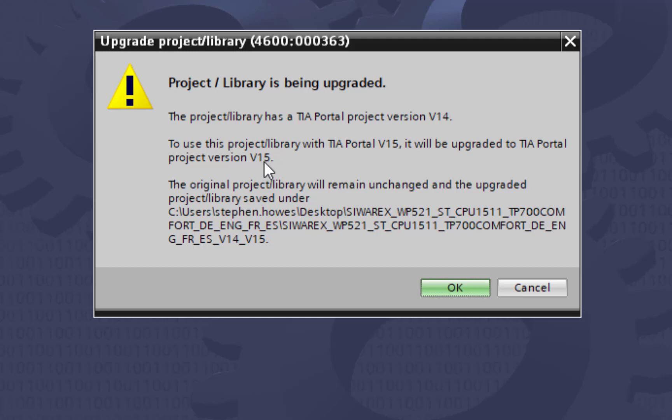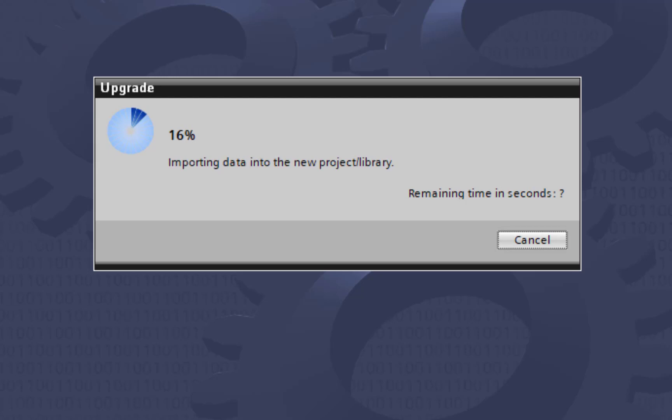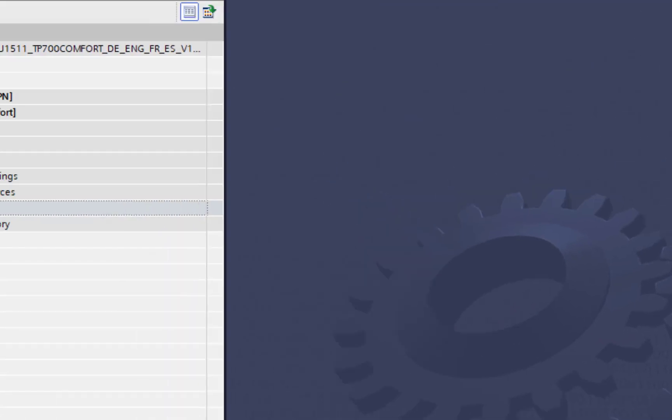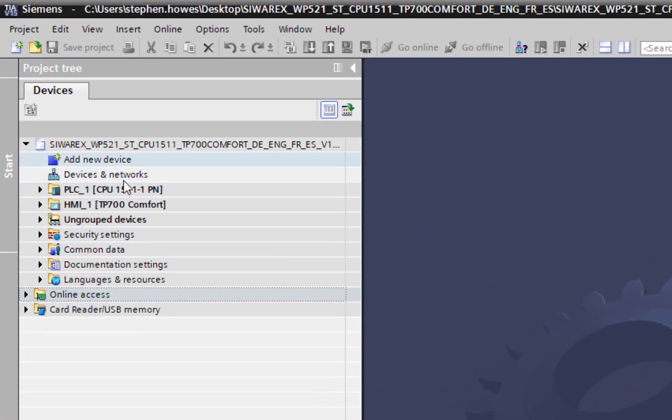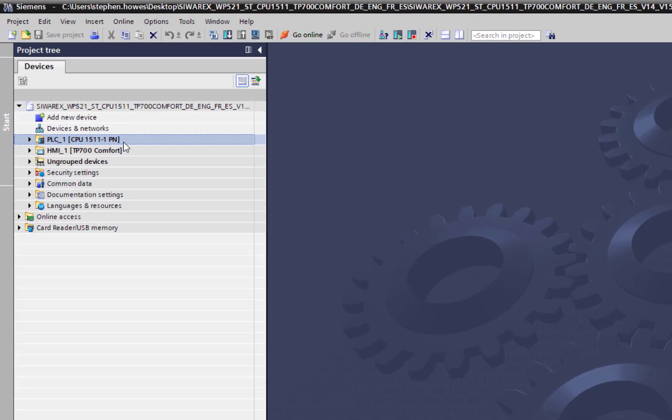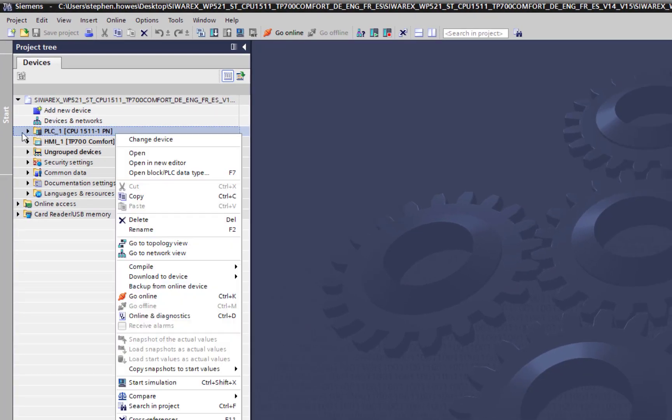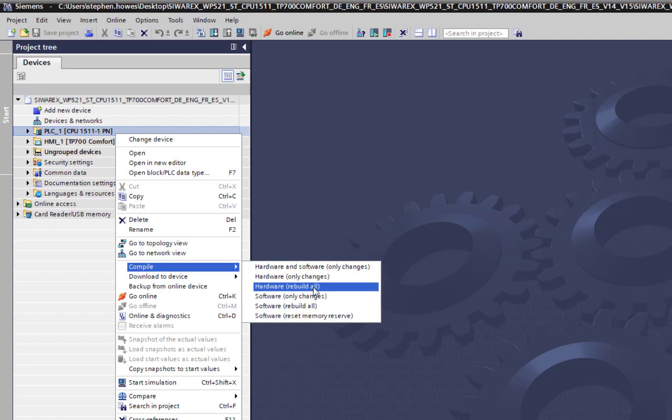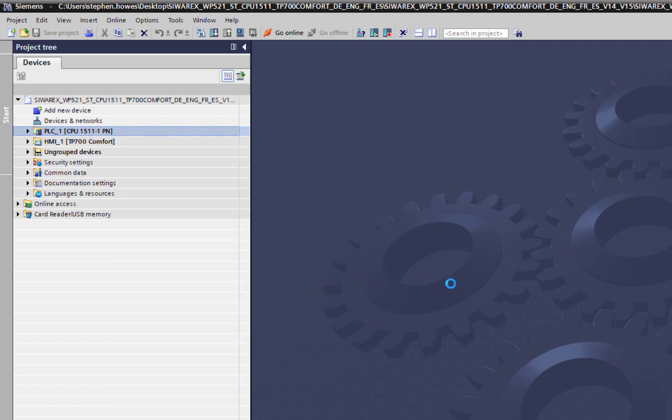It's found that I'm running version 15, so if we just open that it will upgrade my project. Before you save the project, and this is really important, you must compile both the PLC and the HMI. If you save it before you compile then it actually hasn't finished the upgrade. Go to PLC compile and do software and hardware.